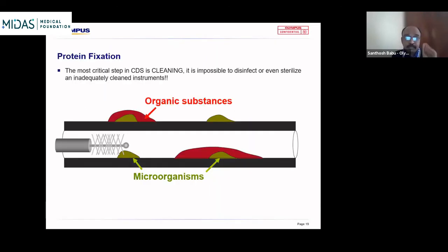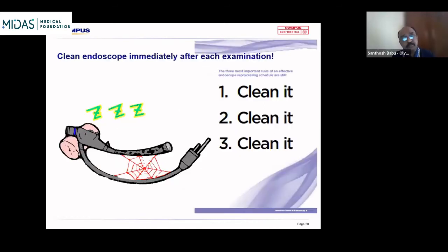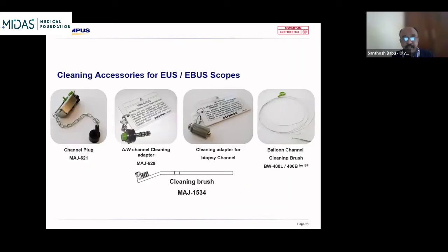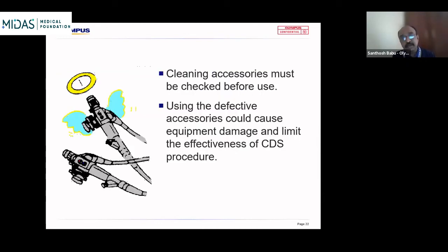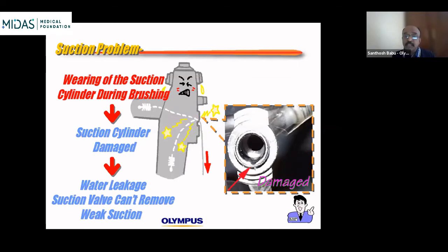Cleaning is the most important step. So gross debris has to be removed. 90% or 95% of the bioburden is taken care of when you do a proper cleaning. So the mantra is clean it, clean it, clean it. A lot of accessories are involved, brushes, adapters, tubes. Make sure that they are proper and functional before you use them on your scopes. If it has a dent, or has no bristles, please don't use it. It can damage the scope. One common thing: my suction is ineffective. Yes, the suction cylinder, if you can see, is all shaved off. Most of the technicians are trained, they know how to handle the brushes. If it is not being done properly, your suction cylinder gets shaved off, and then over a period of time suction is ineffective.